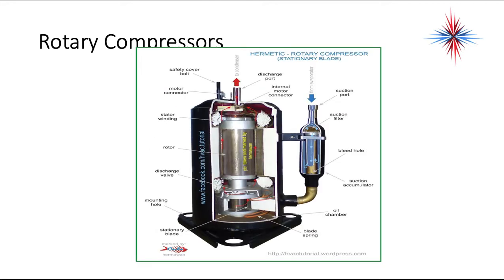This is an example of the rotary compressor. Okay, so we have our discharge up on the dome. We have our low from the evaporator, our low pressure coming in the bottom. As this off-center rotor rotates, it compresses and pushes the refrigerant out through the top. There's valves up here, and it forces it into the discharge at a higher pressure.